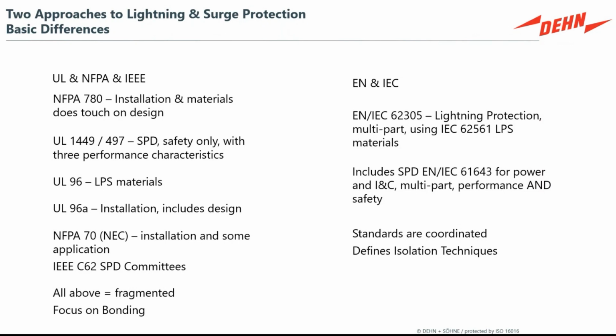They provide protection measures, and it's what we saw on page 1. It's the air terminals, down conductor systems, the grounding systems, the application of surge protection, shielding, bonding, isolation. Those measures are defined within the standards. And so you'll have NFPA giving you an indication for using UL materials, and you'll have IEC giving you an indication to use IEC approved materials.